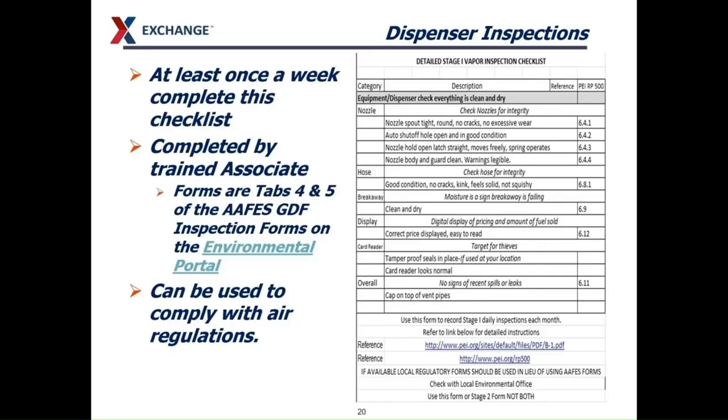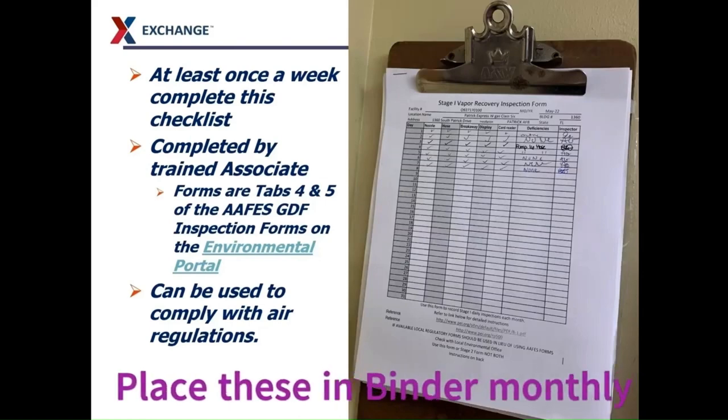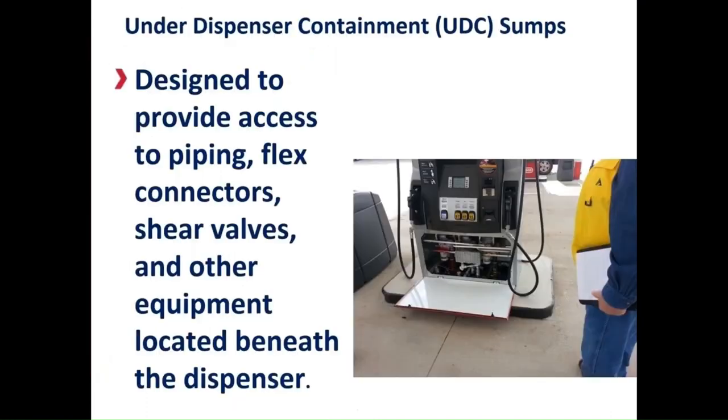The outside of the dispenser is covered by the Stage 1 Vapor Inspection Checklist. Basically, what you are looking at is the nozzles, the hoses, the breakaways, the display, the card reader, and the overall area inside the dispenser. Dispenser sumps — we call those the under-dispenser containment sumps, or UDC sumps. Under-dispenser containment sumps are designed to protect the piping that goes into the dispenser. They are also designed so that any fuel that comes from the dispenser will be contained and not enter the environment.